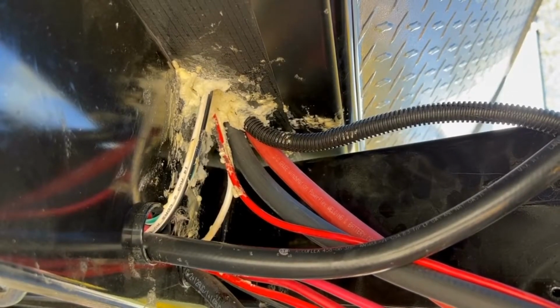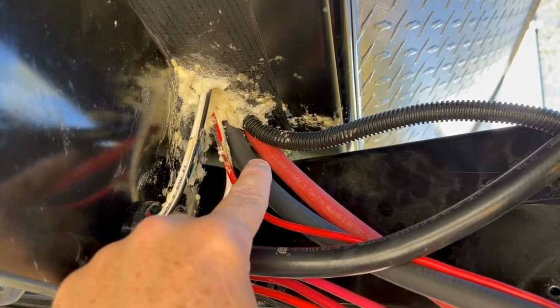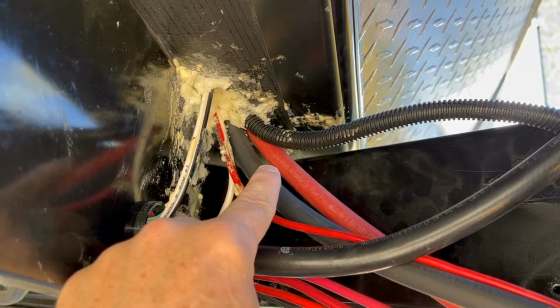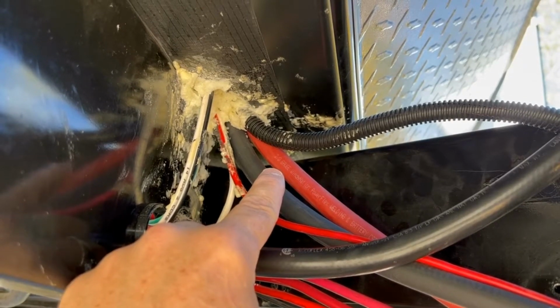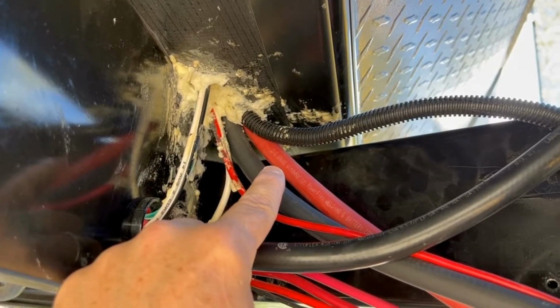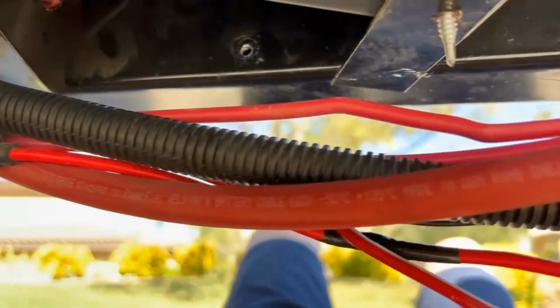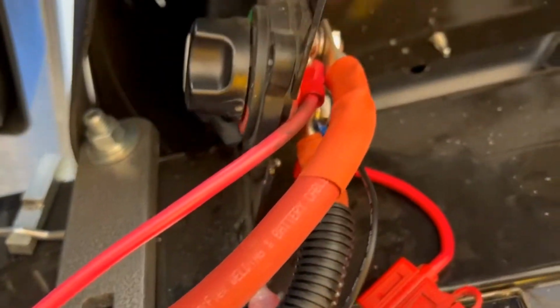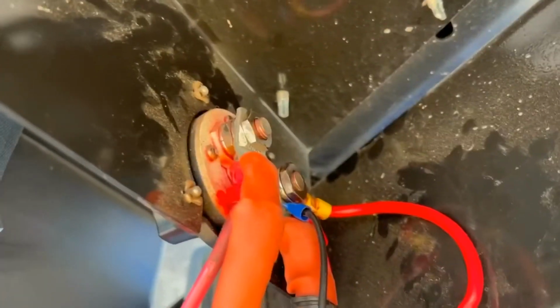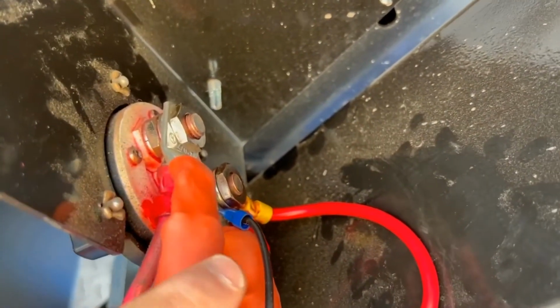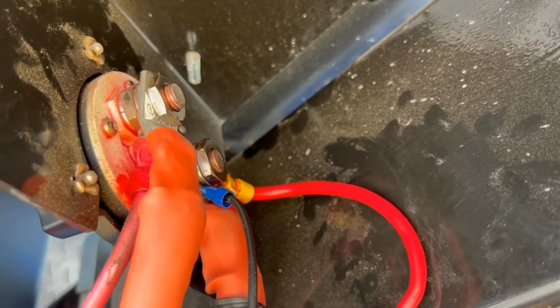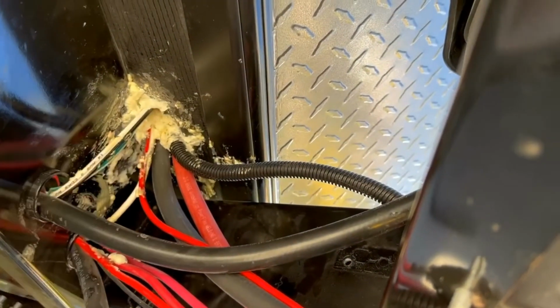All right, here's what we did outside. We've got a new 2-aught gauge cable coming down from the inverter, goes through the cabin, down through the floor, comes all the way down through here and up to the battery disconnect and into the back of the battery disconnect. And from the battery disconnect, we have another 2-aught gauge cable that comes down all the way and goes back up into the cabin.